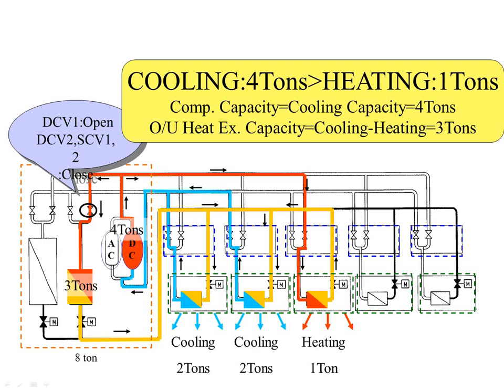So I have 2 zones that want 2 tons of cooling, right? Those are going to reject 3 tons of their heat outside through the outdoor unit, and they're going to reject that 4th ton into the zone that wants some heating, right? So I've always got as many evaporator coil surface areas as I have condenser coil surface areas, if you will. I'm getting 4 tons of cooling for the heat rejection price of 3 tons, for the compressor pumping power of 4 tons. I'm getting 5 tons of total work done here. This is why these systems become very efficient in the heat recovery mode. Instead of running a furnace or a boiler to do that heating, I'm just taking some of my waste cooling heat and dumping it over into that heating zone. That's the basic premise here.